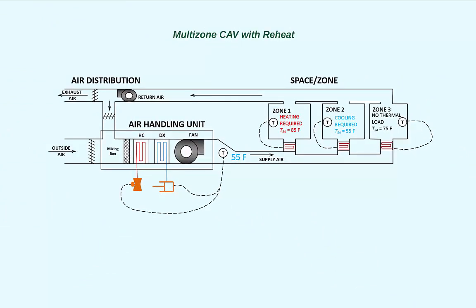An example of when this might be needed is apparent in our multi-zone CAV schematic. Let's say we are trying to create 55-degree discharge air. The unit installed was designed in order to take 80-degree mixed air and cool it down to 55 degrees. But what about on a relatively cool day when the mixed air temperature is only 57 degrees? If we were to run the DX unit at full speed, the air would cool down quickly, the unit would shut off, then the air temperature would rise, forcing the DX unit to turn on again. This causes short cycling, which is terrible for the equipment and burns the compressor out quicker. Therefore, many times DX units employ one or more of the following controls to meet part load conditions.